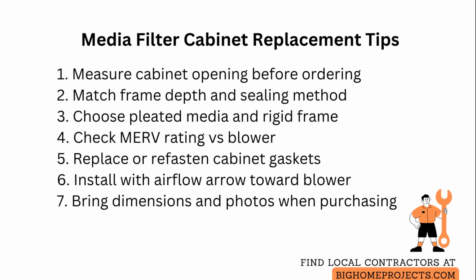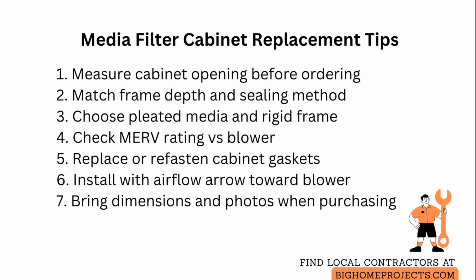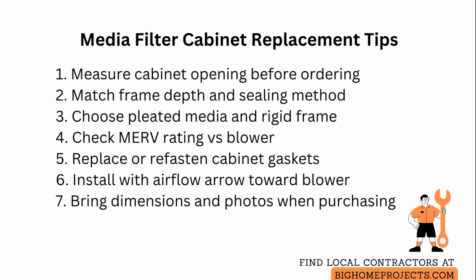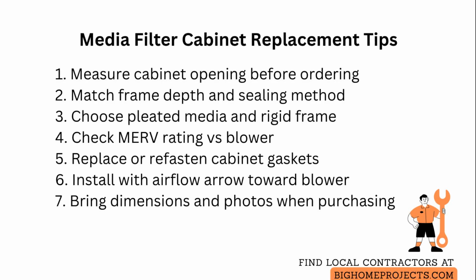Choose a filter with a pleated media pack and a rigid frame for longer life and stable pressure drop. Check the minimum efficiency reporting value rating that your system supports. Higher efficiency media improves particle capture but raises resistance, so ensure the blower can handle the extra static pressure.